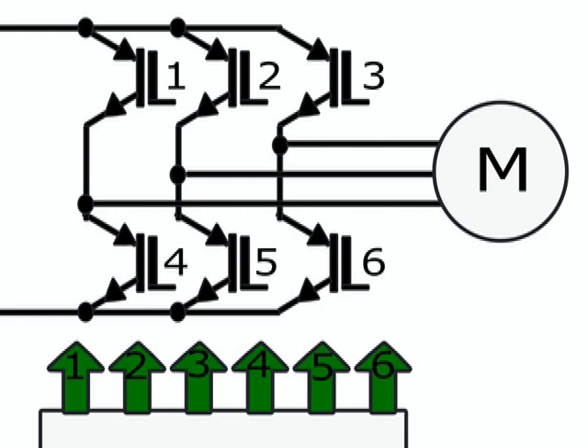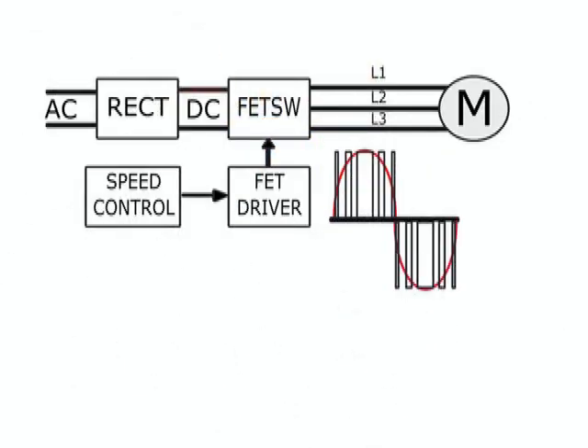In this case, a three-phase motor. Generally speaking, the frequency inverter controller takes AC energy from the power line and converts it to DC, then generates its own sine wave at a different frequency, which can be adjusted according to the desired speed for the motor.